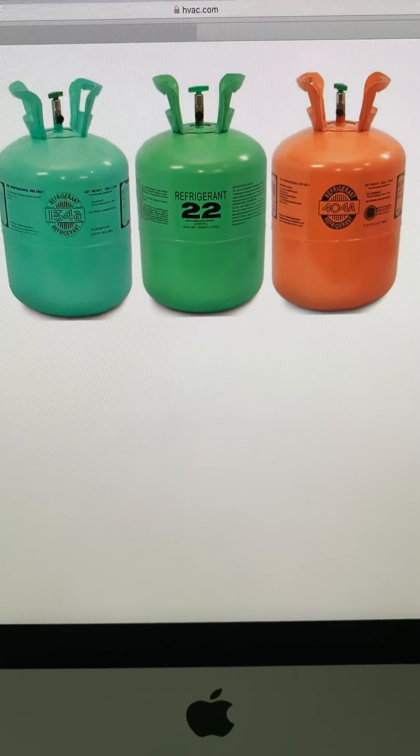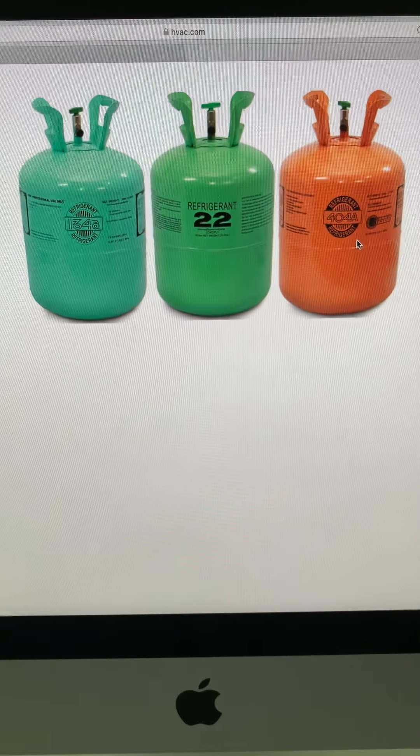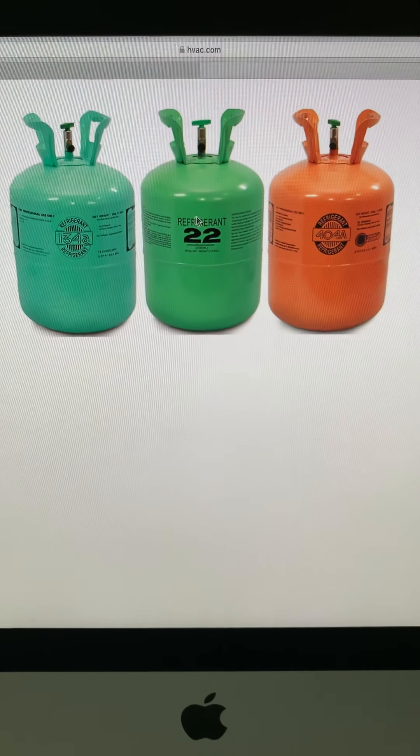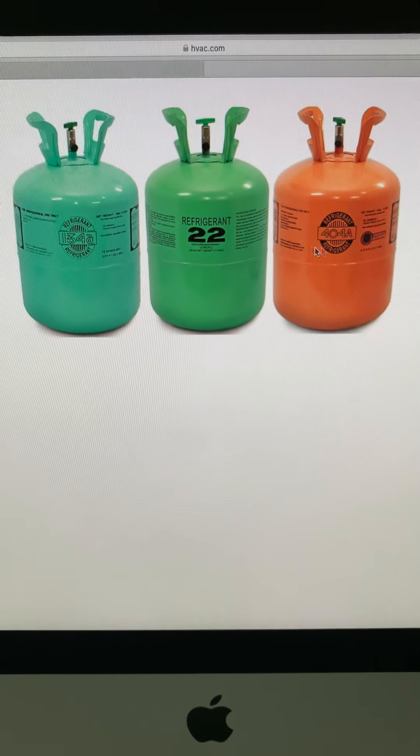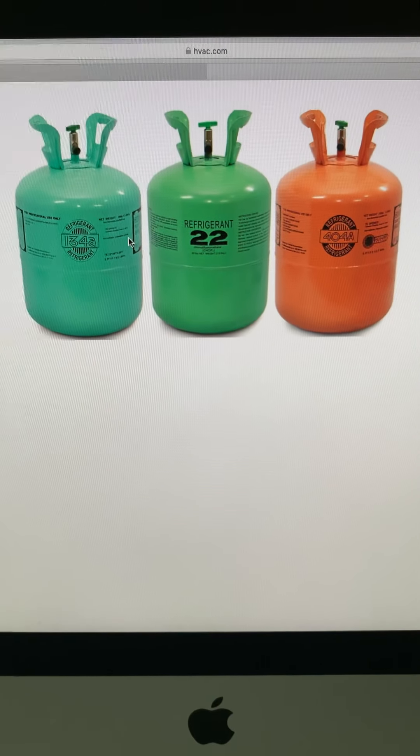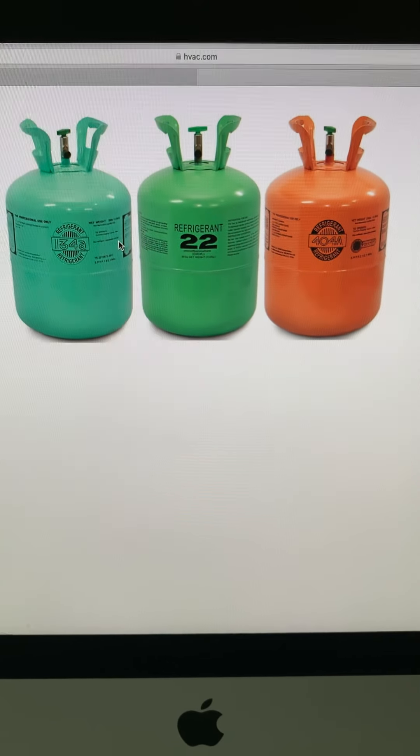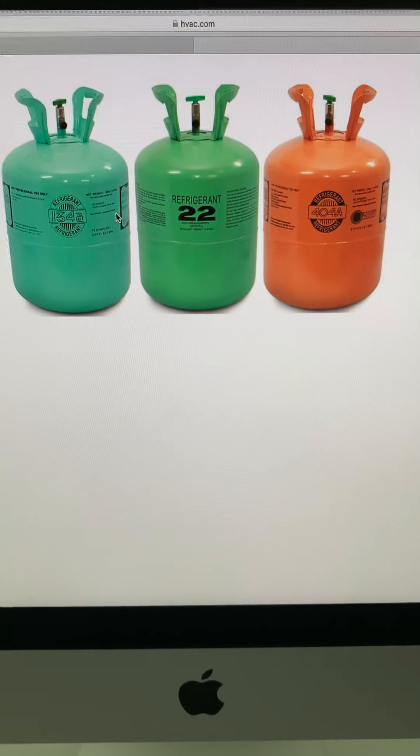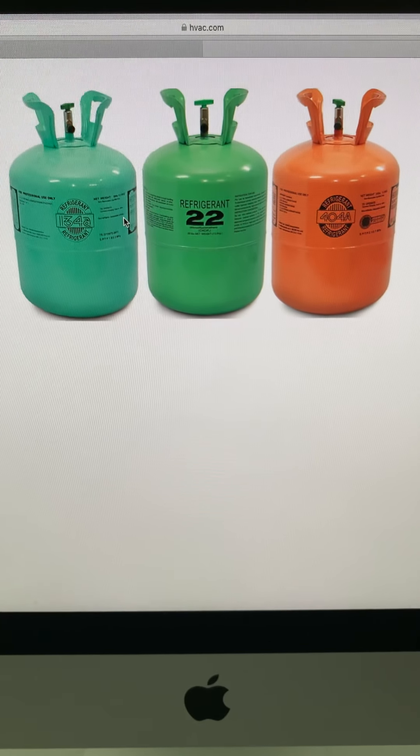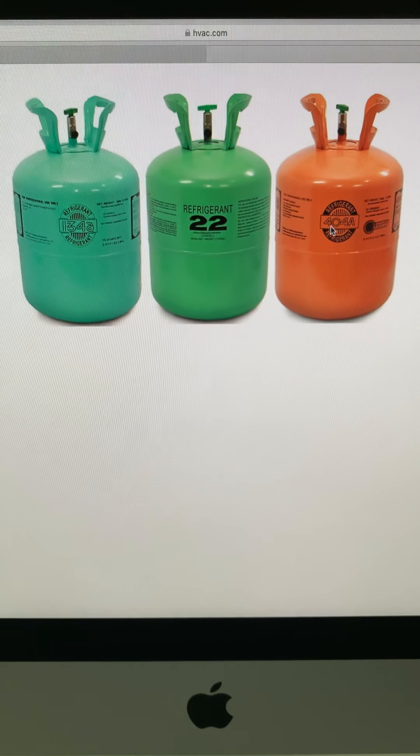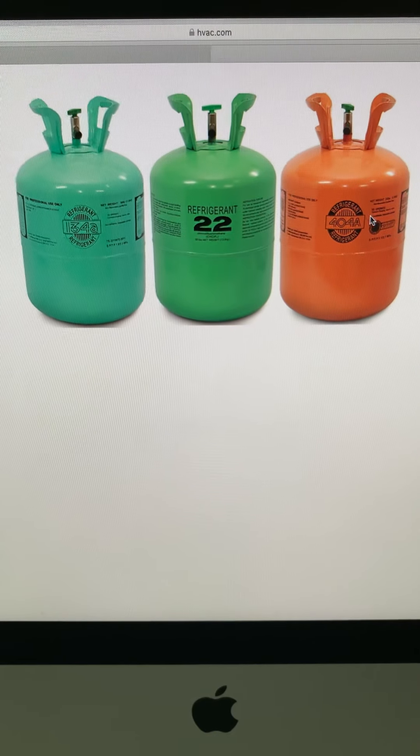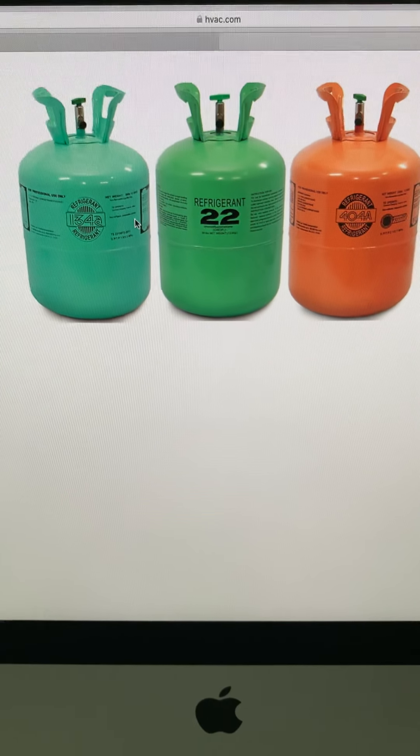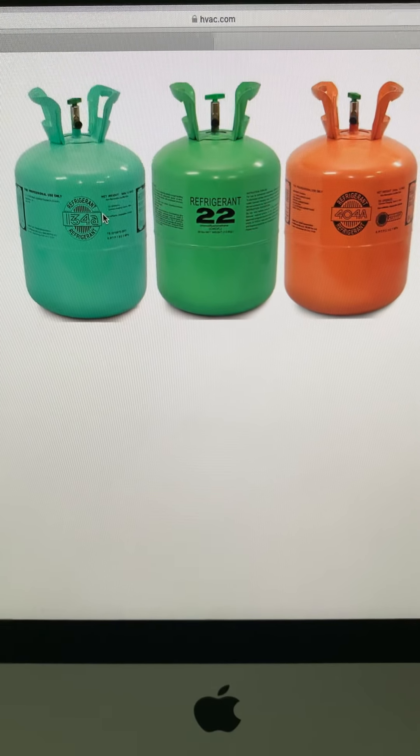These two gases use different units, so you can't simply swap out gas in the unit. For instance, if you look at Thermo King units, they will be designed for either 404A or 134A. For frozen, 404A; for refrigerated, 134A.